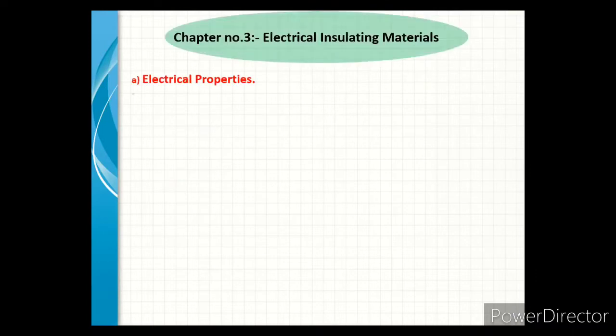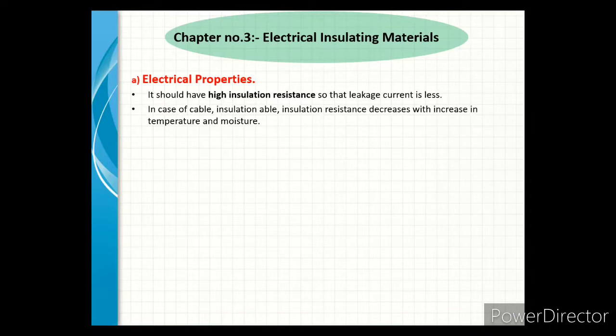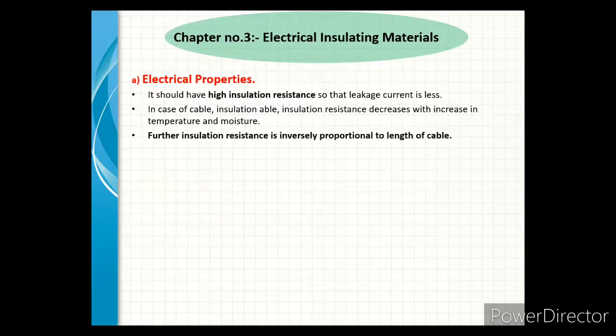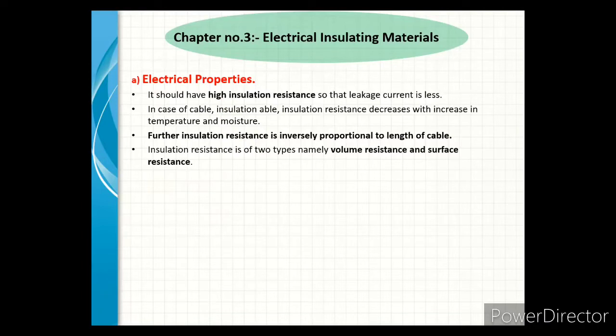First, we see the electrical property. It should have high insulation resistance so that leakage current is less. In case of cable, insulation resistance decreases with increase in temperature and moisture. Further, insulation resistance is inversely proportional to the length of cable. Insulation resistance is of two types: volume resistance and surface resistance.